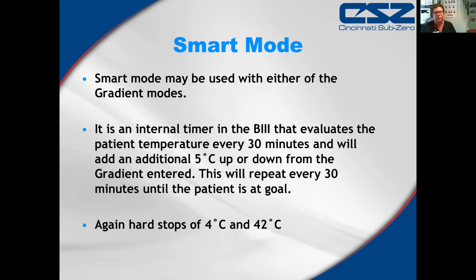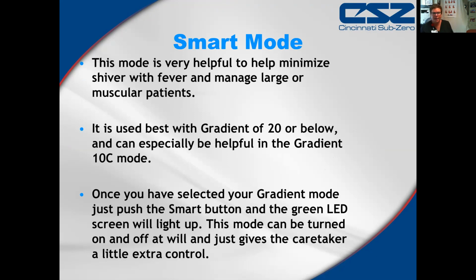So I think the smart mode is a really good thing to use. It's helpful, it minimizes fever, it minimizes the shivering associated with fever, and it helps you manage the really muscular patients a little bit better, because oftentimes they are more difficult to achieve targeted temperature. The smart mode is best used when we use the gradient variable of 20 or less. So a little more narrow difference between the patient and the temperature. And it is very helpful in the gradient 10. So once you've selected your gradient mode, you simply push the smart button, a green LED light will come on, and that just gives the care provider a little bit extra control over the temperature.